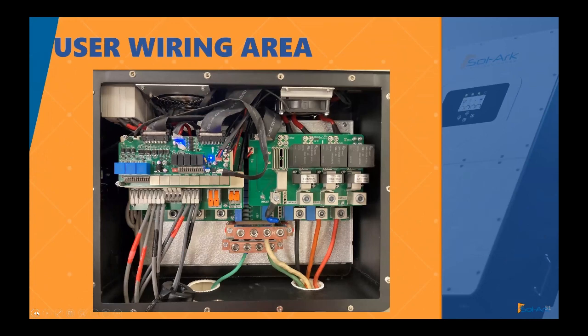I would also like to say that in the MPPTs, we have a 500 volt and 36 amp limit. So if you go above this, there's a high risk of damaging the inverter. So I would stay under that limit. Another thing is that we can pass through 200 amps or up to 72 kilowatts. So that's a lot of power. And basically what you can see here is the user wiring area.